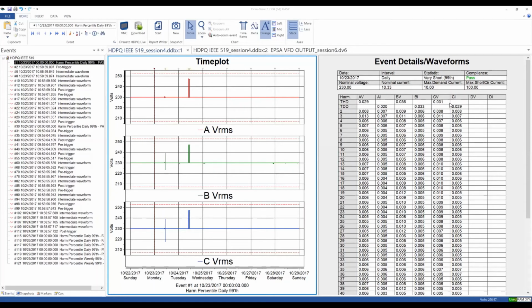And if you look on the right, this report is done in a pass-fail format, using the statistical analysis engine of HDPQ, and all this is done in the instrument. You are viewing recorded data here in DranView, so there's no post-processing done in DranView other than potentially creating a report for a printout and a Word version of your report. This is a pass-fail report, the very short time harmonic report, and you can see the date, it's just a few years ago, and this is a pass report.